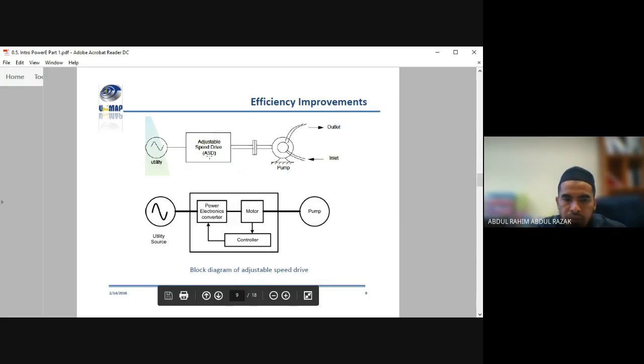Okay, when we apply this kind of ASD, there will be an efficiency improvement. Like I told you before, if we directly tap to the pump from AC, it can work, but we shall have issues of efficiency. Means that the degradation of your pump efficiency will be very bad, compared to if you tap in an ASD to the pump. So you can raise up the speed slowly, and you can stop gradually. You will not face an issue of inrush current or inrush flows.